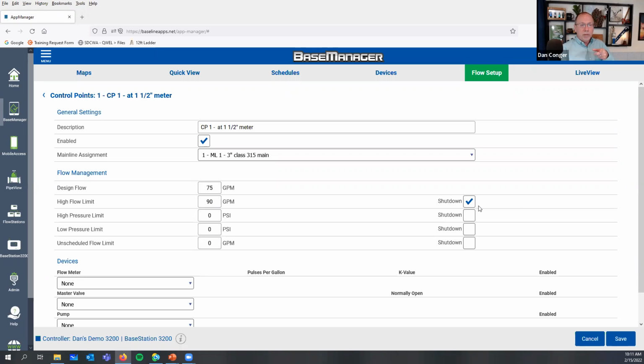So I also like that point, Tracy, of during the trial period, don't shut down and see what happens and kind of get with it. Okay. So 9 times out of 10, once your system is established, you do want to shut down. I'm going to skip the pressure limits, but we could do something with that. That's not what we're working on today. Here, I'm going to put an unscheduled flow of 15 GPM. And the way I define unscheduled flow is flow the controller doesn't know about. So bleeding a valve, a quick coupler, those are two prime examples of unscheduled flow.